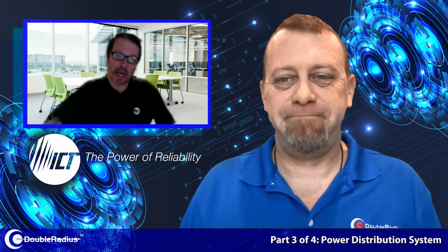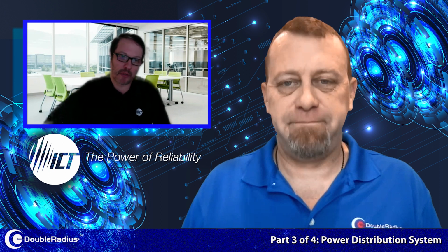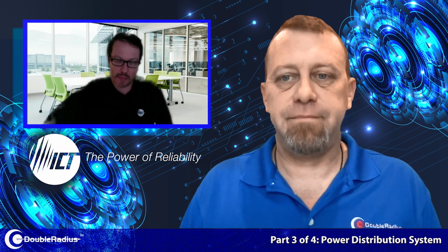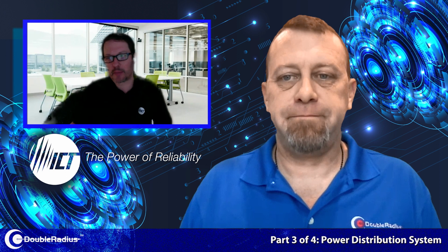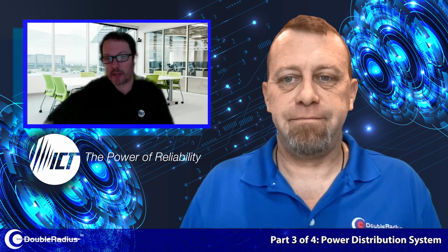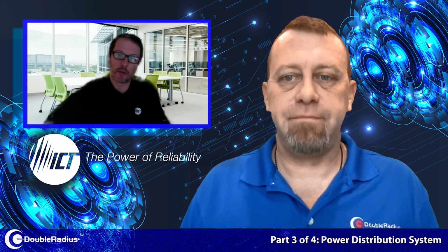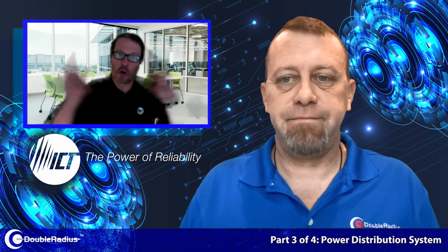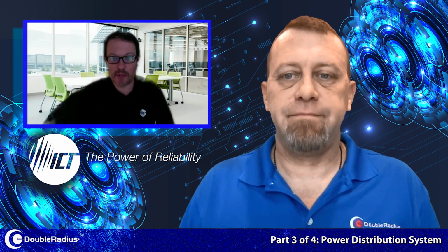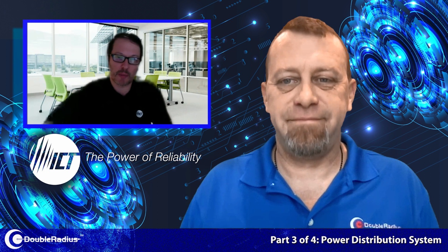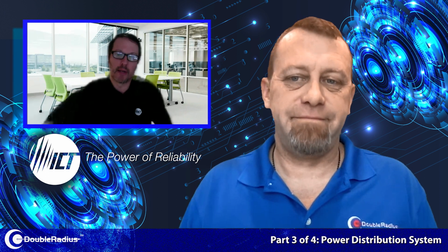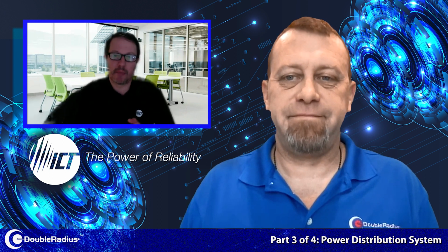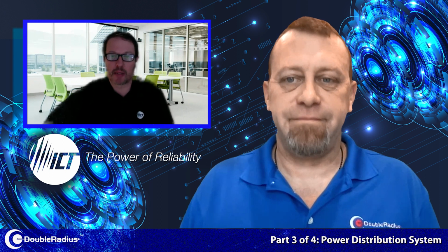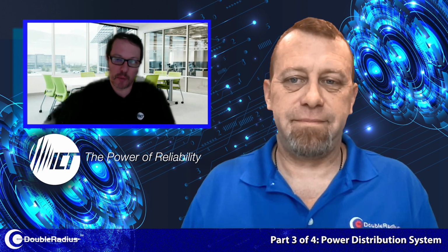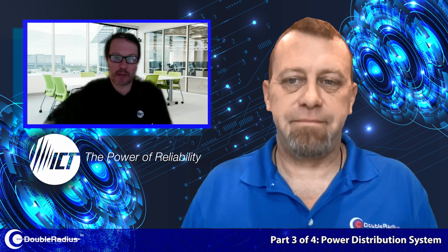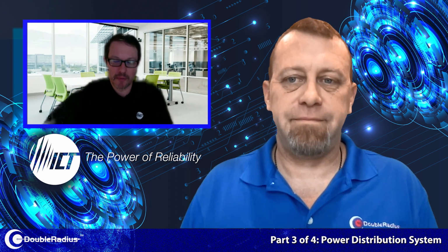And then we have a 20 output distribution, which provides 10 outputs on bus B and 10 on bus A as well. And that's for customers that have quite a lot of load devices they want to distribute power to. So rather than having two 12 output devices to give you 24 outputs, taking up 2 U of rack space, we have a 1U device that provides 20 fuse protected outputs. So a little bit for everybody, to try and suit all application requirements.